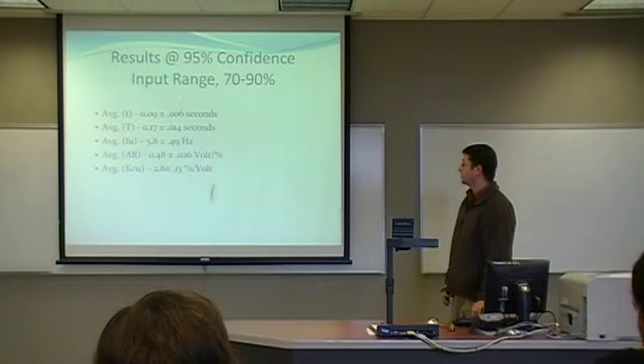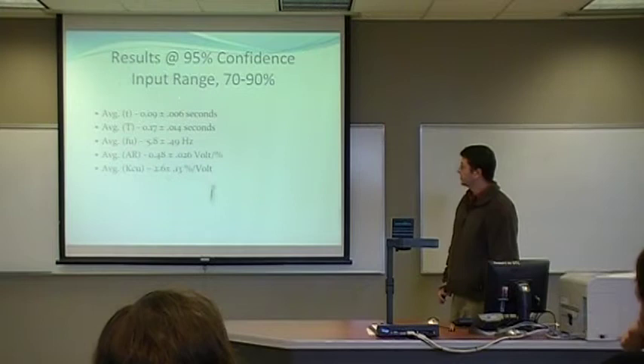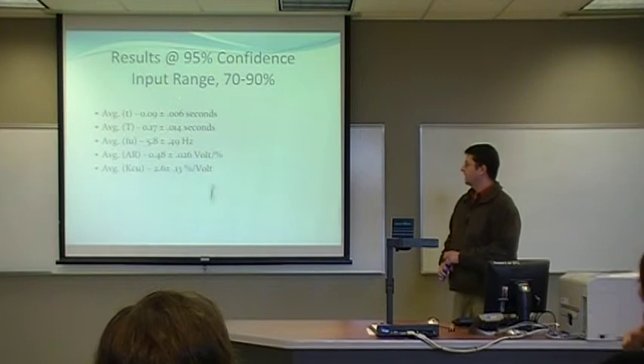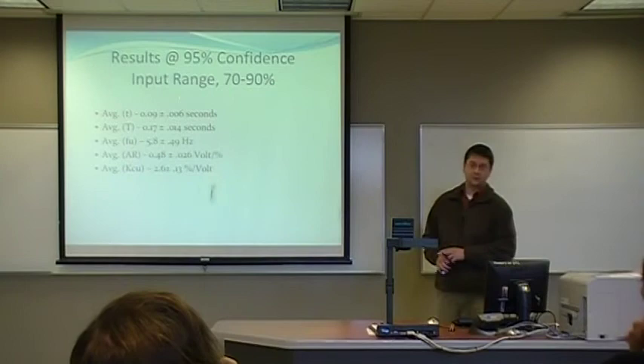5.8 hertz plus or minus about a half a hertz. However, the amplitude ratio is significantly different than the previous one. Before it was 1.5, however, in this one it's only 0.48, and that's plus or minus 0.026 volts per percent. And the average controller gain, ultimate controller gain, is 2.6 plus or minus 0.13 percent per volt.